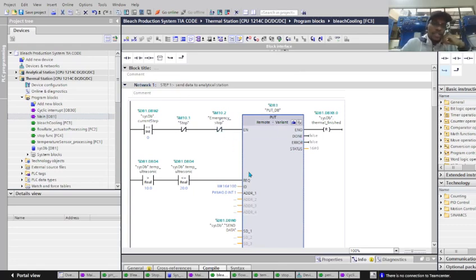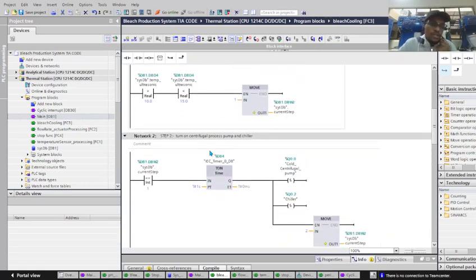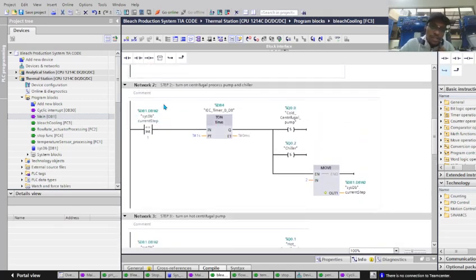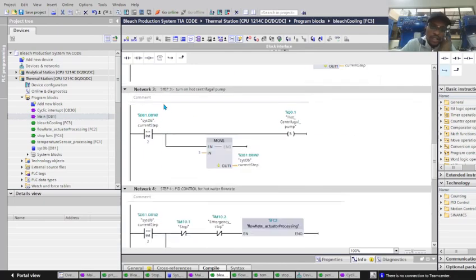So we start by sending, in the first network, data to the analytical station, and it is also resetting the thermal station from the previous cycle. It's sending the data from the ultrasonic sensor to tell the analytical station that the process fluid has flowed from the analytical to the thermal station. And once the process fluid has been received, we start the centrifugal pump, that is the process pump that runs the process fluid throughout the system, and we also start the chiller.